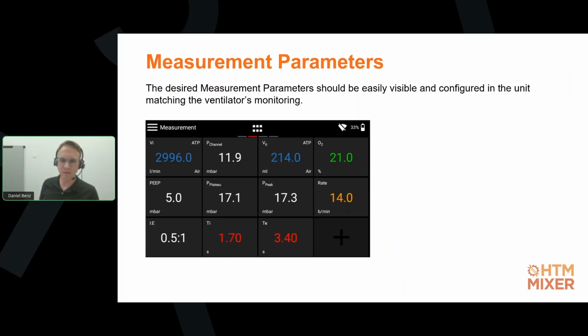verifications. For example, one ventilator might use the term P peak for the maximum pressure during the inspiratory phase, while another one uses the term PIP, which stands for peak inspiratory pressure. But this is actually the exact same thing. That's why gas flow analyzers can typically measure and calculate more than 25 different parameters, and usually they can display them in multiple different units. For example, pressure in centimeters of water pressure, millibar or Pascal.